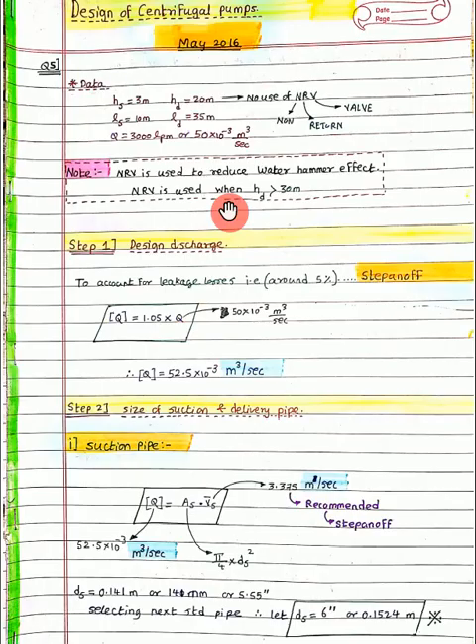So if the delivery head is greater than 30 meters, use of non-return valve is mandatory so as to avoid the water hammering effect. So moving on to the design procedure, the first step is calculating the discharge.